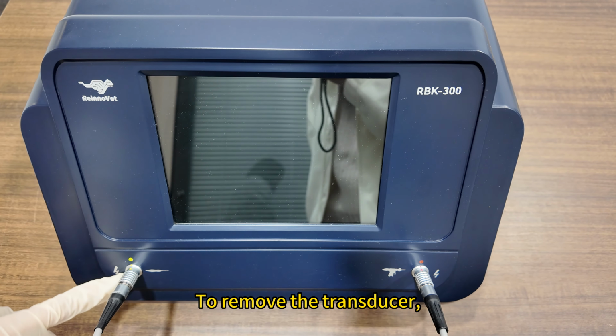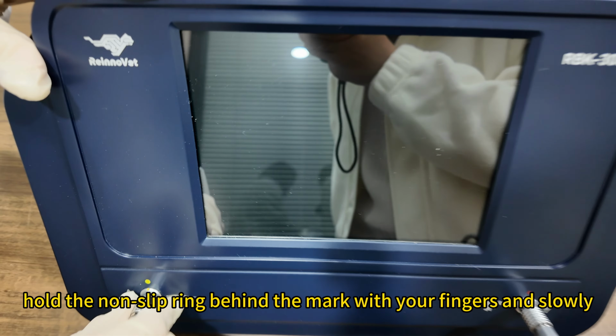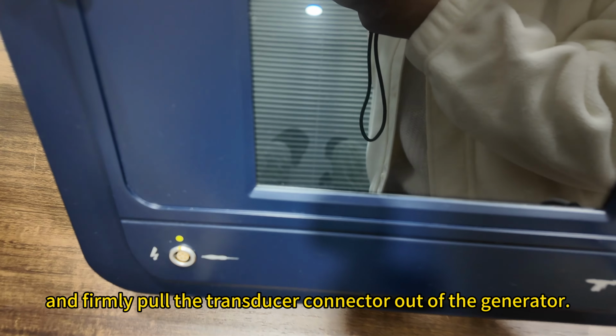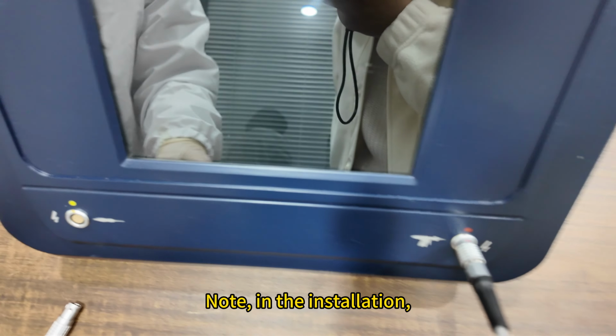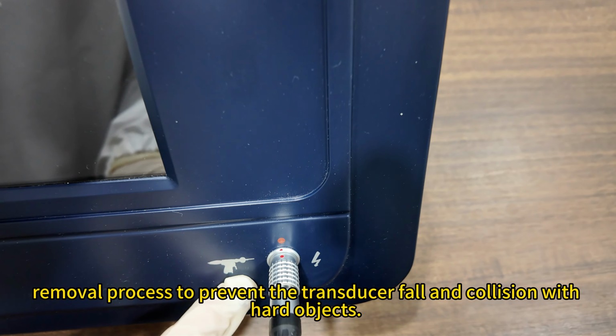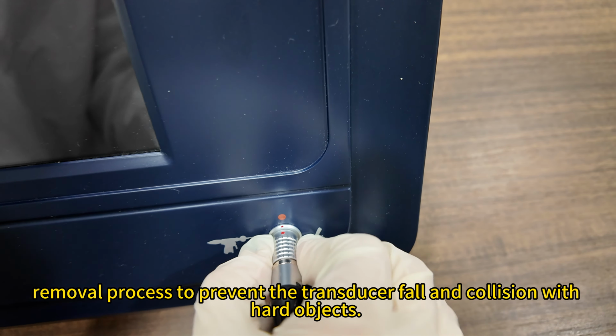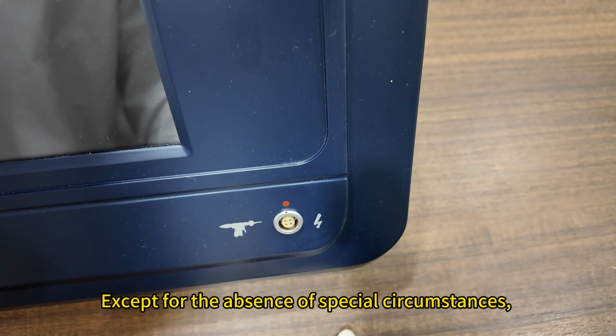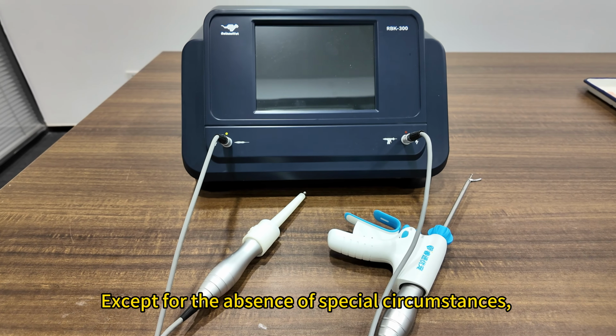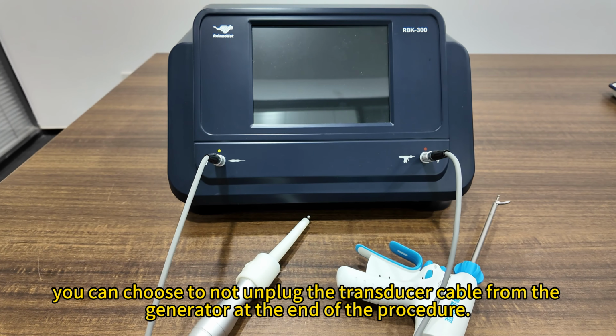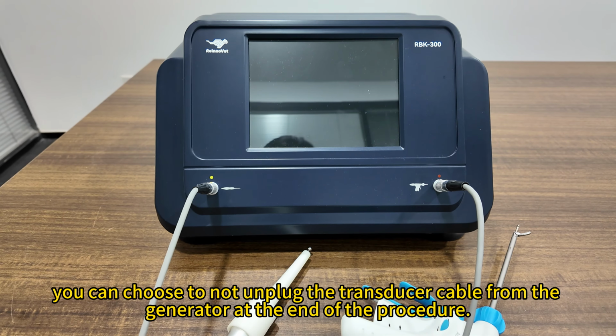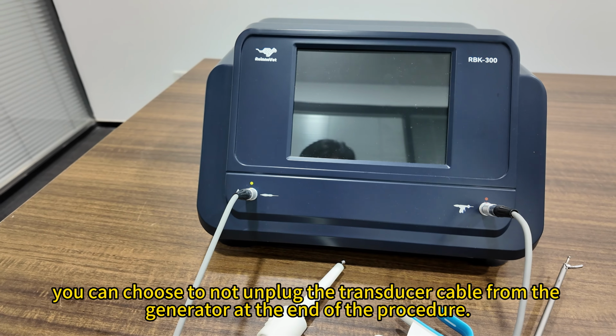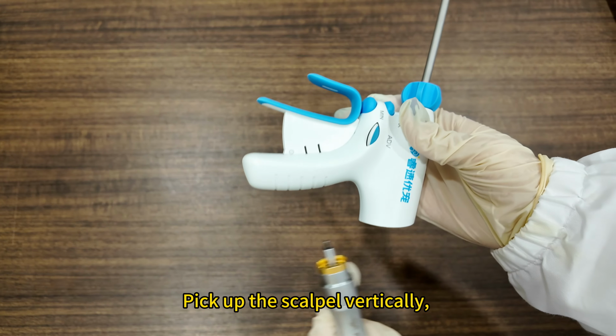To remove the transducer, hold the non-slip ring behind the mark with your fingers and slowly and firmly pull the transducer connector out of the generator. Note, in the installation and removal process, prevent the transducer from falling and colliding with hard objects. Except in special circumstances, you can choose not to unplug the transducer cable from the generator at the end of the procedure. Pick up the scalpel vertically.